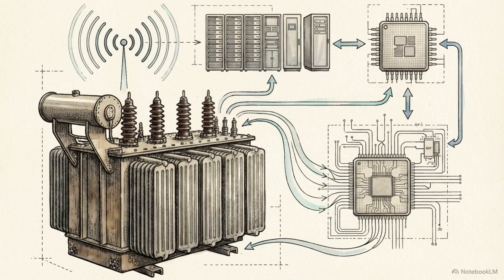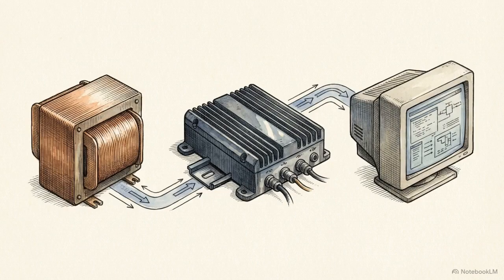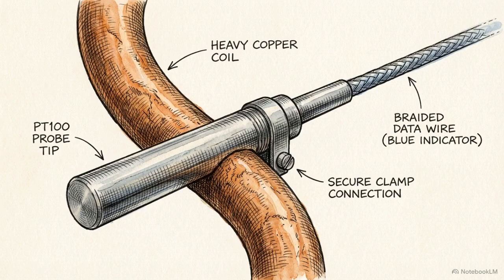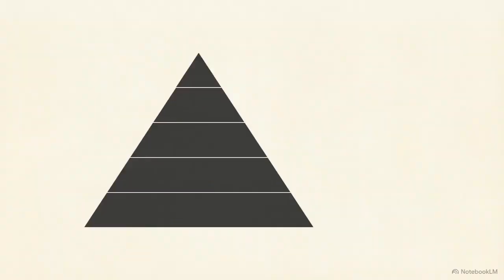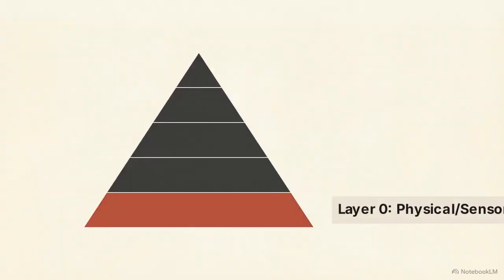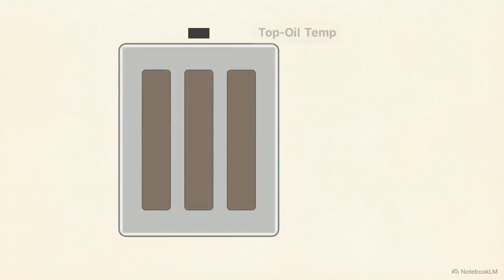Protecting the asset requires moving away from time-based preventative maintenance. Instead, engineers must adopt condition-based predictive maintenance, relying on the Industrial Internet of Things, or IIoT, to monitor the equipment continuously. Executing this requires architecting a continuous, operational technology-grade IIoT data pipeline. It begins by extracting raw thermal metrics directly from the physical copper coils and securely transmitting them to a central dashboard for real-time analysis.